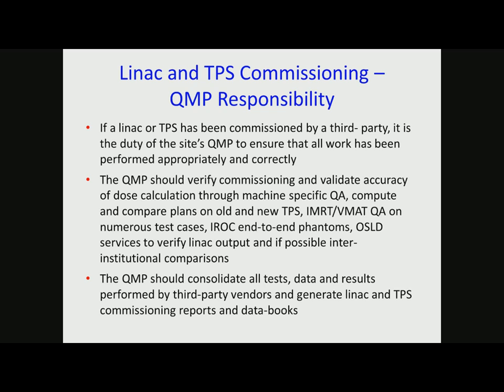So the QMP should consolidate all tests, data, and results performed by third-party vendors and generate Linac and TPS commissioning reports and data books. John mentioned that in his talk. And that's very important. There are many sites I have visited that have nothing. I asked them, where's your commissioning report? They pull out their Eclipse or Pinnacle or whatever, and on the screen they show me the modeling. And I said, that's not sufficient. You need to show me a commissioning document. And what have you done to check this commissioning from some third-party person?